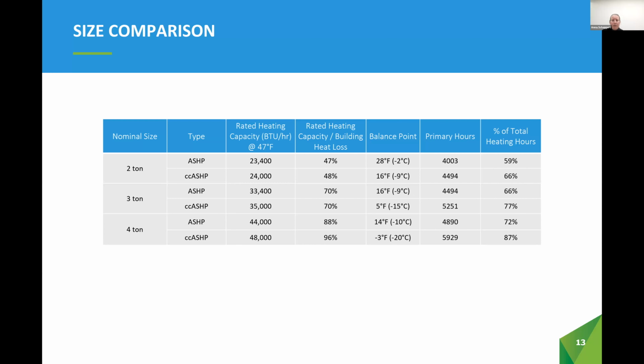It's crucial to identify your goals when choosing an air source heat pump. It is reasonable to size a heat pump for a building's cooling load, and there will still be shoulder season heating benefits by doing so. Systems can also be sized to balance the heat and cooling loads. This would result in a unit which might be slightly oversized on cooling, but would provide heating down to lower temperatures. Or systems can be selected to meet the majority of the building's heating.